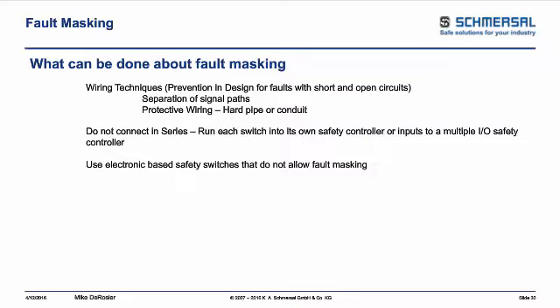All right. So I guess the first question for you, Mike. Can guards be attached with thumb screws to allow for ease of preventative maintenance? They can be attached with thumb screws if you put safety interlocks on them, because when you attach it with thumb screws, they're no longer a fixed guard. They're a movable guard, just like having a door on a hinge to gain access. But the other aspect that you have to be careful of when making that decision, even if you put a safety interlock switch on there, is the one thing that you had just said in that question, which was for maintenance reasons.